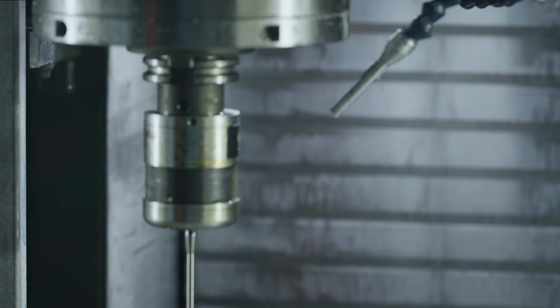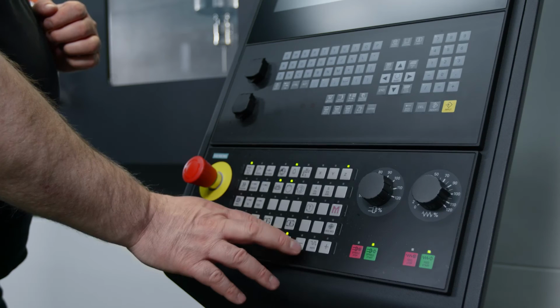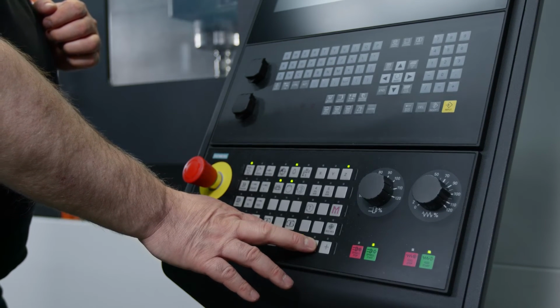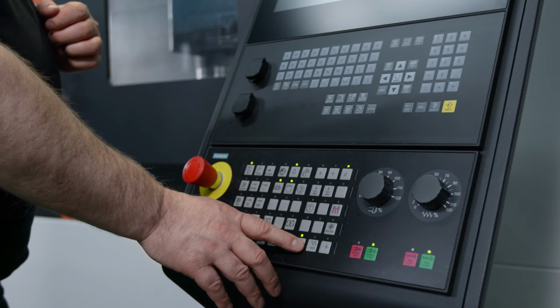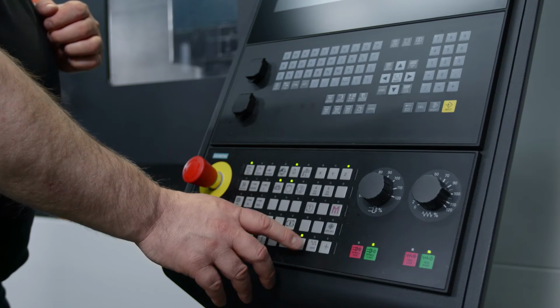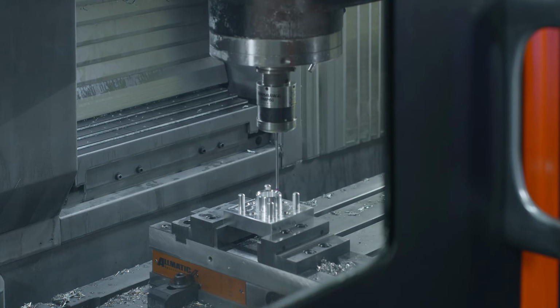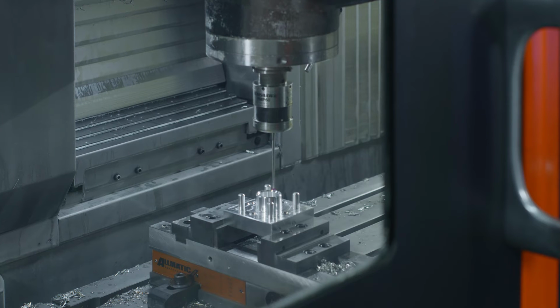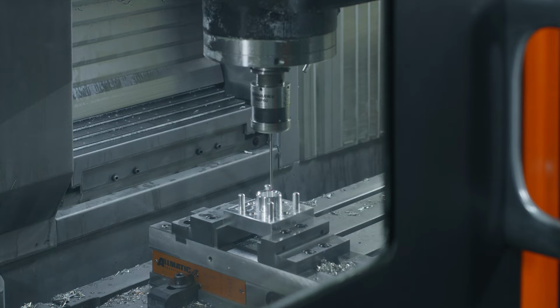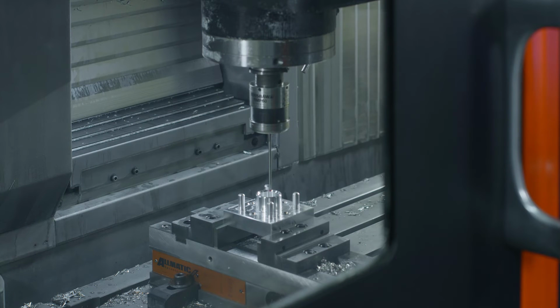Next, the 3D probe will be positioned above the drill hole where we want to specify the 0 point. All you have to do is move it approximately to the right position in the hole. There's a measuring or safety range that can be adjusted flexibly, of course, so that it doesn't begin to measure exactly at the edge, but is first switched into the measuring feed rate.